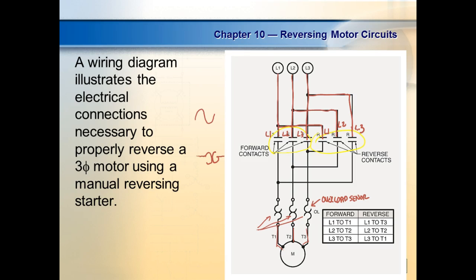So you don't switch L1 and L3 on the top of the relay because that would create a short circuit. We always switch on the output of the relay. That's where we do our switching. Not on the top, on the what? On the output side. Everybody okay? Lightened up a little bit, didn't it? So we notice on this one, let me change color.